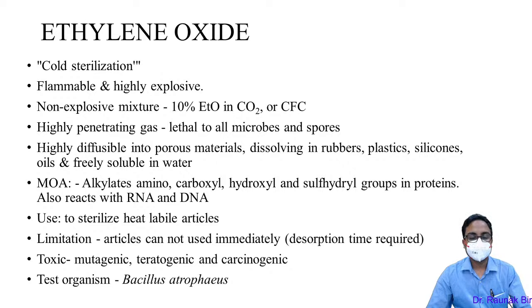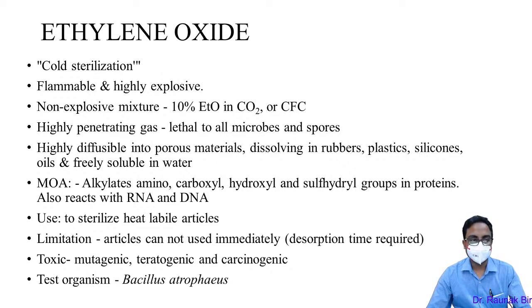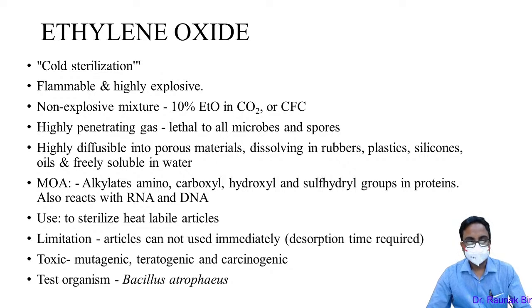Ethylene oxide is one of the highest level disinfectants, also known as a sterilant — it is a cold sterilization method. It is a flammable liquid gas and highly explosive, so to render it non-explosive we mix it with carbon dioxide or CFC at 10%. It is highly penetrative and kills most spores and microbes. It diffuses into porous materials, dissolving into rubber, plastic, and silicone. Its action alkylates amino, carboxyl, hydroxyl, and sulfhydryl groups in proteins, rendering them non-functional, and also degrades DNA and RNA.